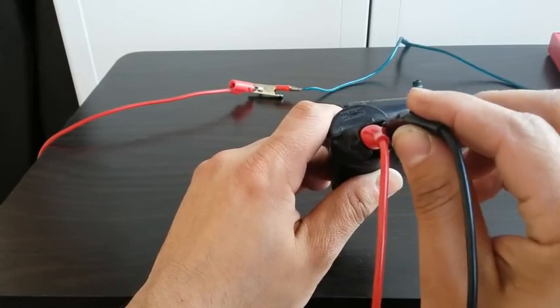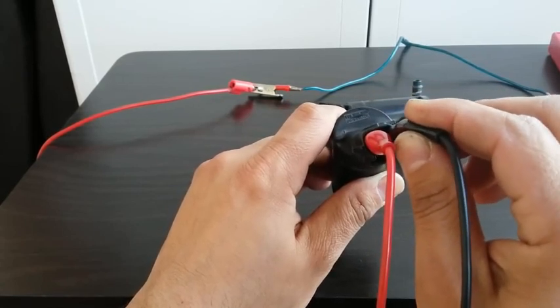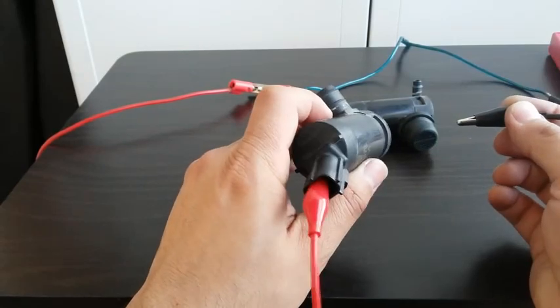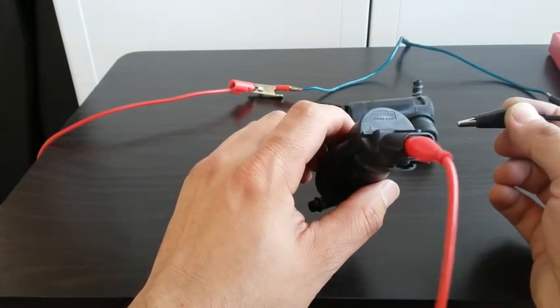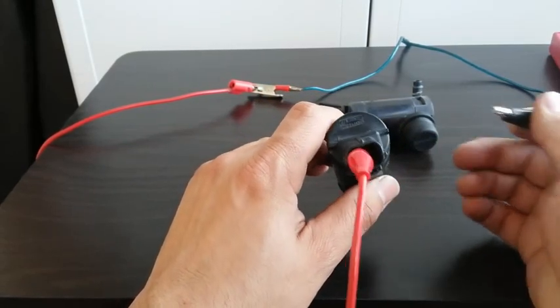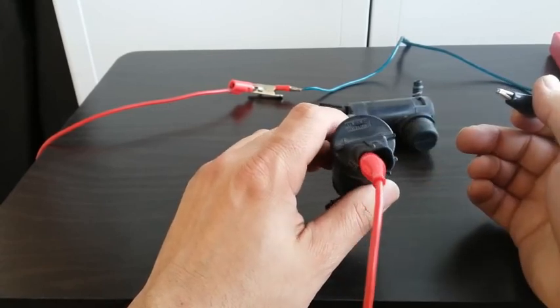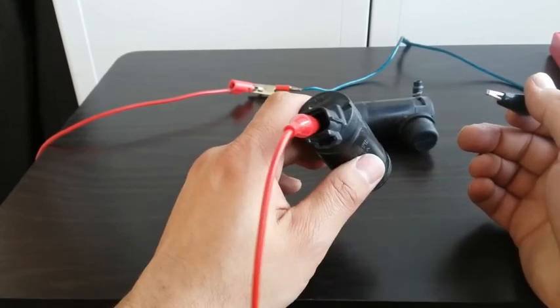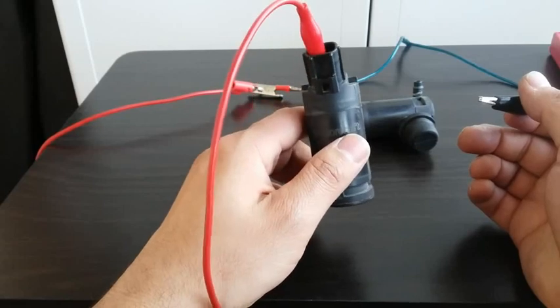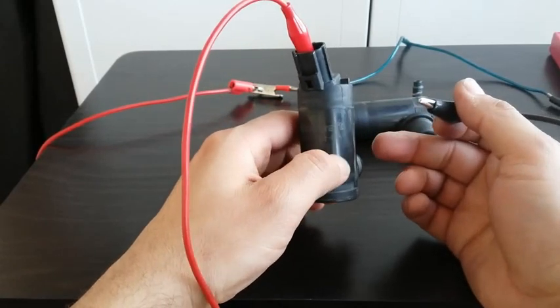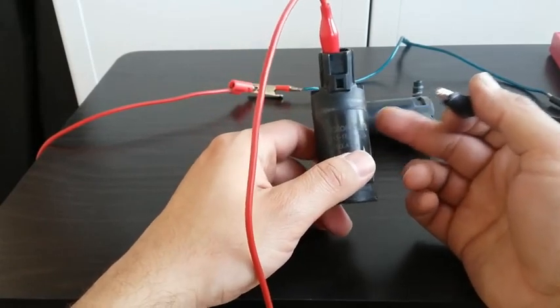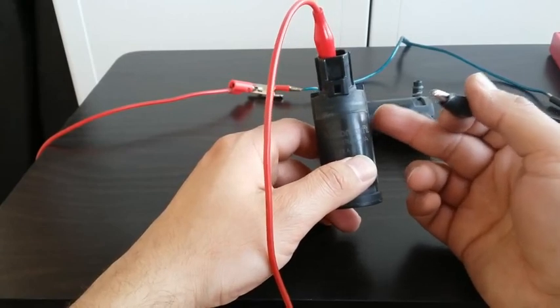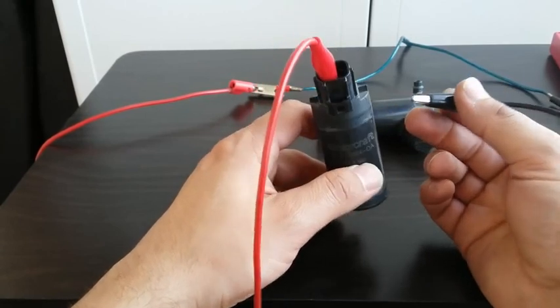I'm going on and off. The motor is not even working. So pretty much this tells us the culprit problem: it is the pump motor. Either mechanically it went bad, or we have some damage on the coil windings on this motor here.